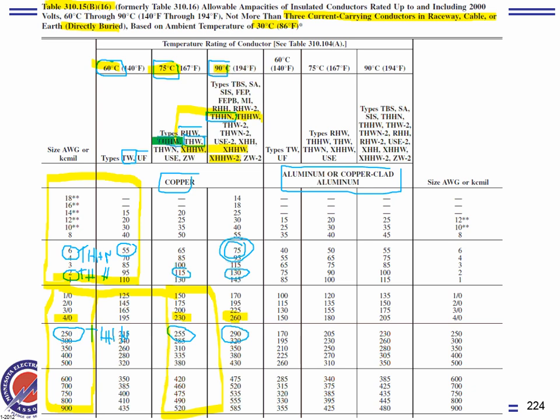Okay, 100 amp. Let's just take 100 amp. Okay, I have 100 amp continuous load. So that becomes what? 125 amp. Everybody knows why, right? You multiply by 125 percent. Okay. Now I need to size a conductor for it. I decided to use THHN.